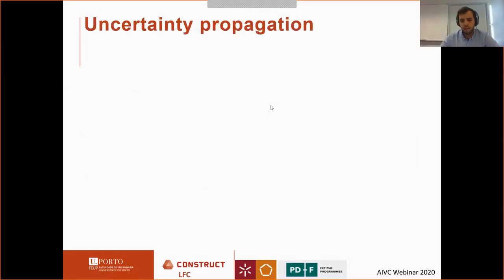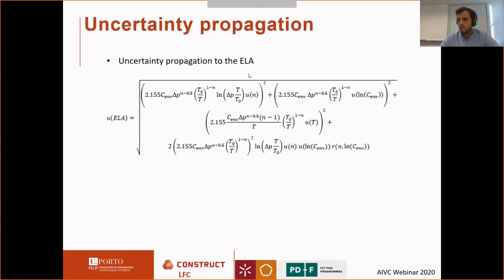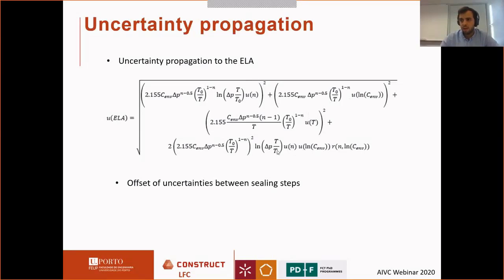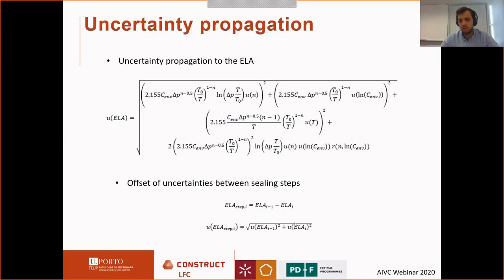How do we propagate the uncertainty from one step to the other? For the effective leakage area we have different components: the airflow exponent, the airflow coefficient, temperature, the second-order effect for the correlation of these two. The offset of uncertainties between sealing steps is incremental — from one sealing step to the next we subtract the effective leakage area of one group of components from the other, but the uncertainty sums, so it accumulates.